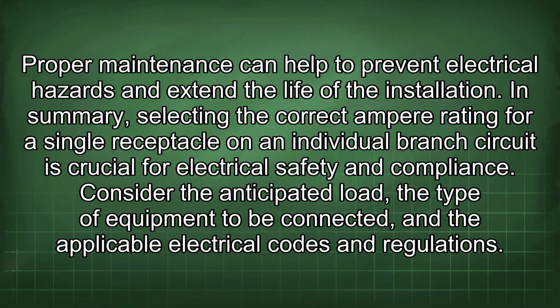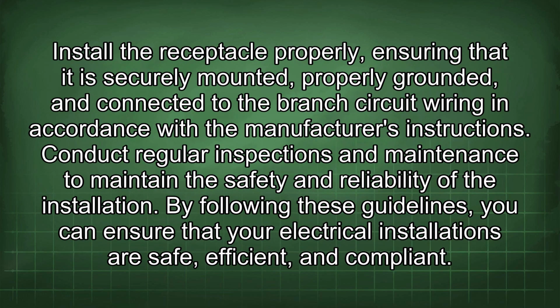In summary, selecting the correct ampere rating for a single receptacle on an individual branch circuit is crucial for electrical safety and compliance. Consider the anticipated load, the type of equipment to be connected, and the applicable electrical codes and regulations. Install the receptacle properly, ensuring that it is securely mounted, properly grounded, and connected to the branch circuit wiring in accordance with the manufacturer's instructions. Conduct regular inspections and maintenance to maintain the safety and reliability of the installation. By following these guidelines, you can ensure that your electrical installations are safe, efficient, and compliant.